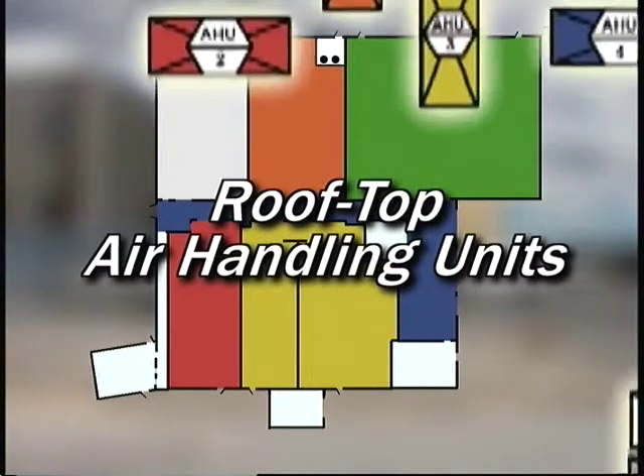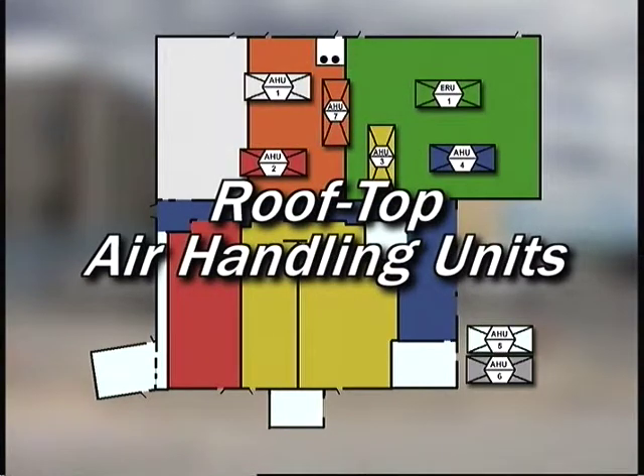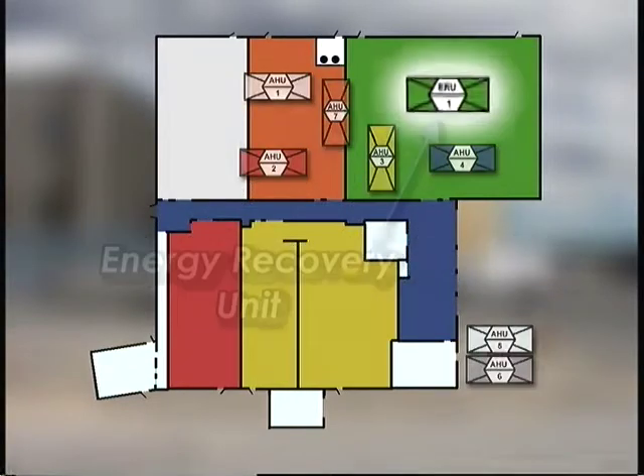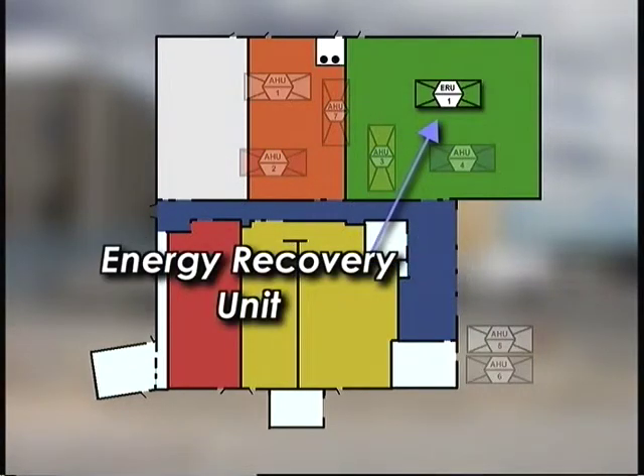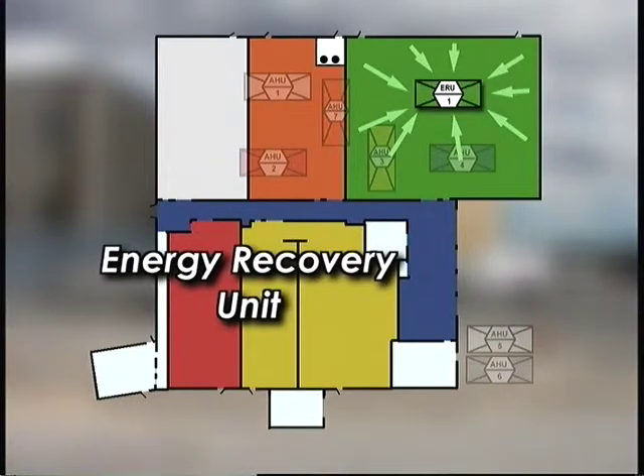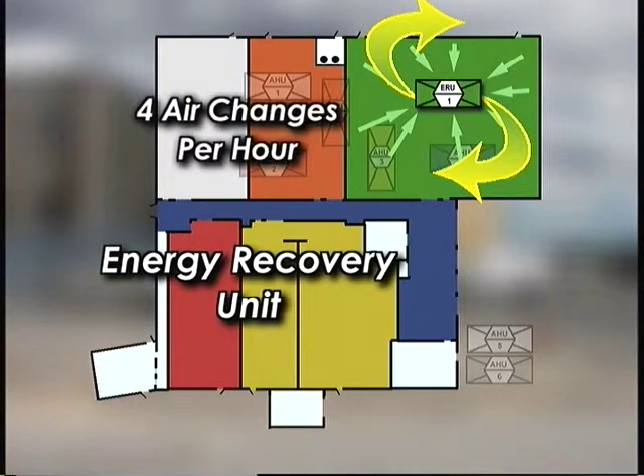Each portion of the warehouse space is provided with a dedicated air handling rooftop or energy recovery unit. The flammable liquid storage area is equipped with an energy recovery unit that does not recirculate air, but provides 100% outside air when in operation. Air is withdrawn from the space served by the same unit and exhausted through a heat recovery wheel at a rate of 4 air changes per hour. Air is completely replaced in the affected space every 15 minutes.